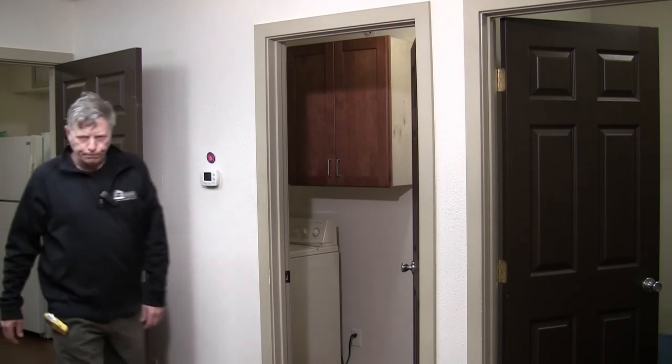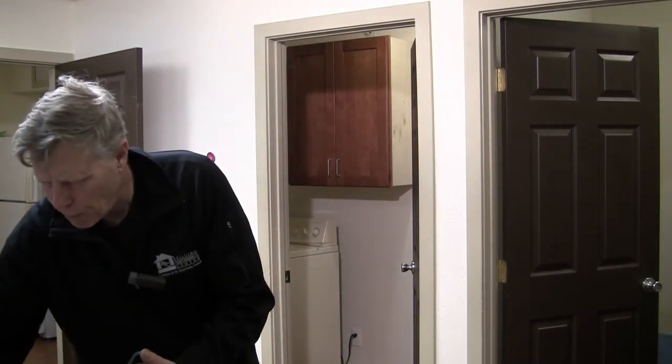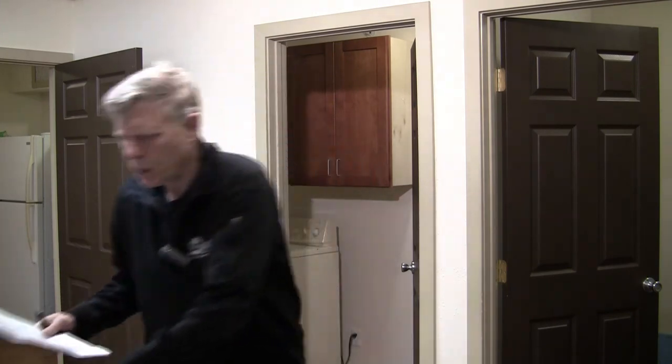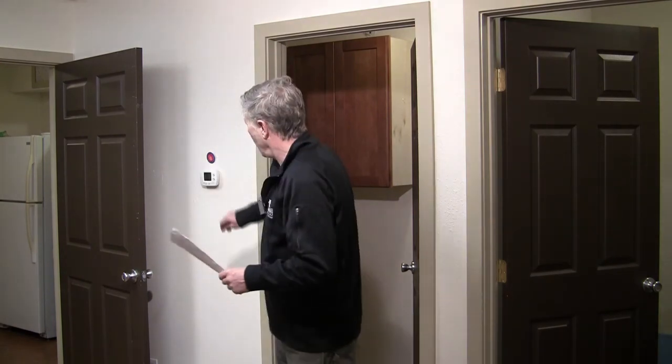Check my manometer here, and we have a pressure of negative 3.2. All right, I'm going to jot that down. That's 5B. The next step is to check air handler impact. So that's line 5C. So if it goes more negative, we're going to leave that air handler on. If it goes more positive, back towards 0, we're going to turn it off. So let's go ahead and check the air handler impact.